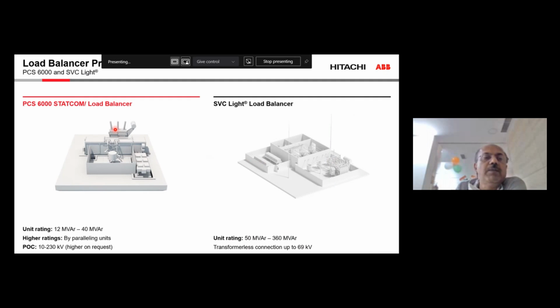You can see that there is a transformer to match the network voltage, and then there is a container-based STATCOM located inside, and there can be some additional filters due to the harmonics, and then there is a cooling system. So this entire solution can be built in the factory, tested, and then delivered to the site. So within the best possible limited time we can commission and switch on the substation in a very short period of time. And this is very modular in nature. Suppose you want to add one station now, and after some years you want to add another station, it is easily possible to augment it.